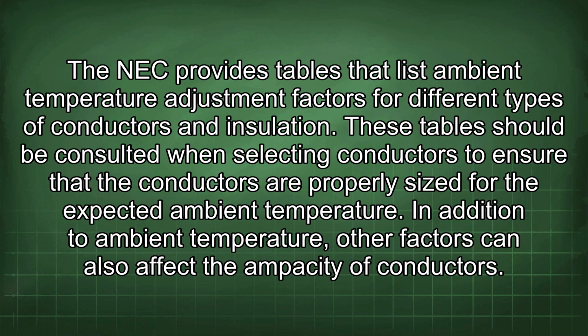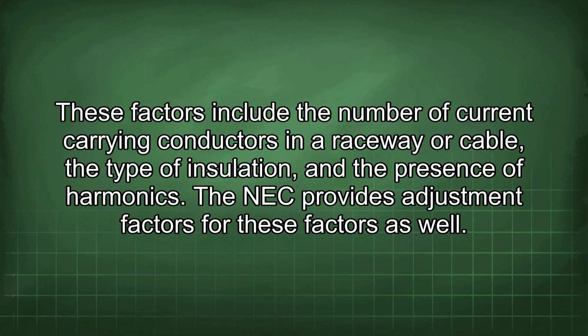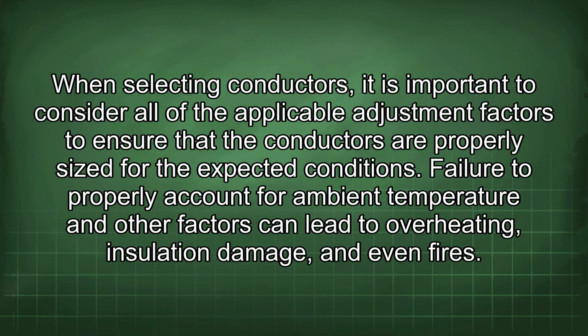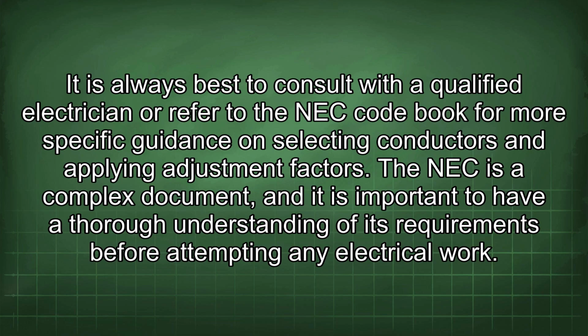In addition to ambient temperature, other factors can also affect the ampacity of conductors. These factors include the number of current carrying conductors in a raceway or cable, the type of insulation, and the presence of harmonics. The NEC provides adjustment factors for these factors as well. When selecting conductors, it is important to consider all of the applicable adjustment factors to ensure that the conductors are properly sized for the expected conditions. Failure to properly account for ambient temperature and other factors can lead to overheating, insulation damage, and even fires. It is always best to consult with a qualified electrician or refer to the NEC code book for more specific guidance on selecting conductors and applying adjustment factors.